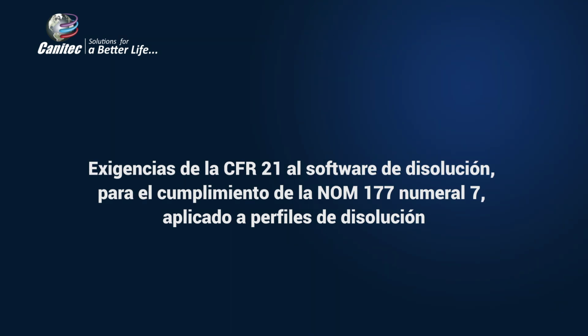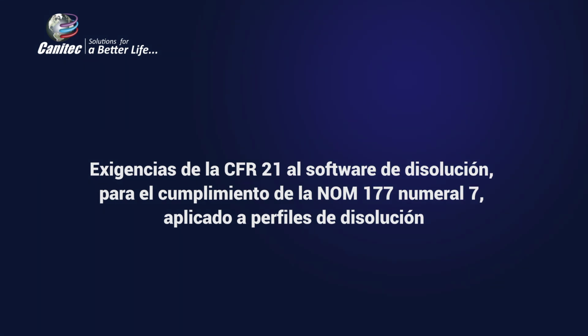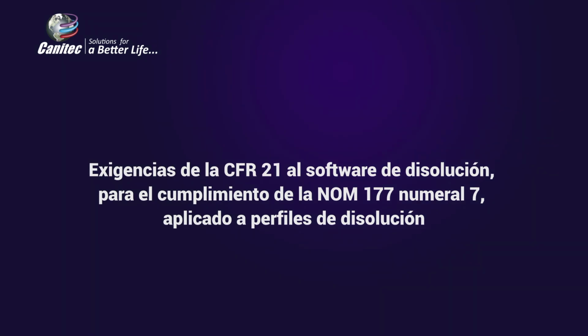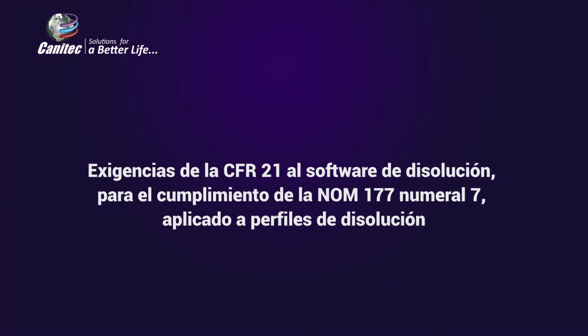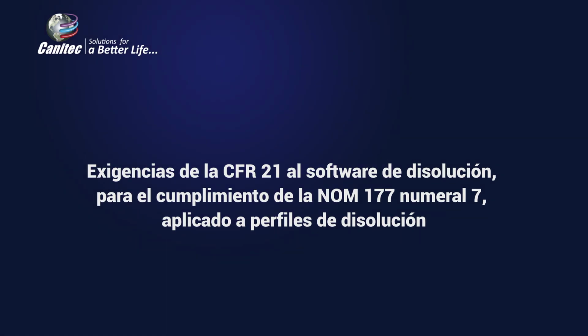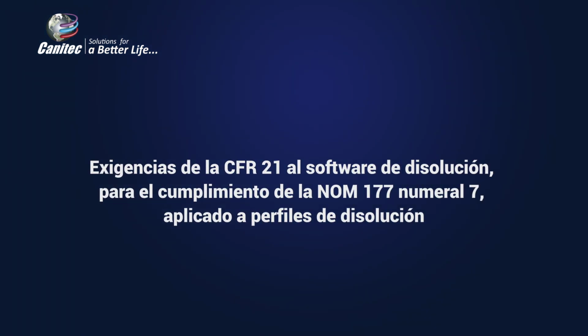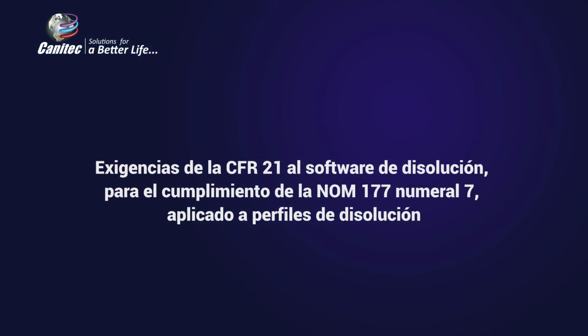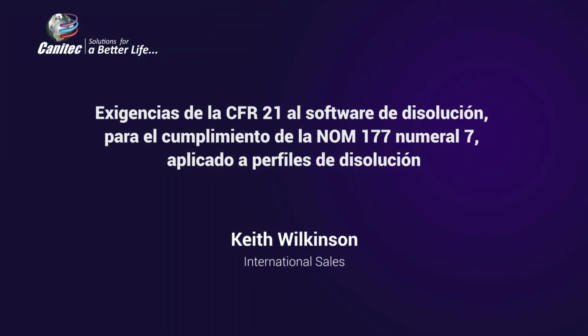On the software as well, if you wanted to, you can see the percent dissolution as the experiment is proceeding. You do not have to wait until it's stopped. And we also have statistics where you can look at the statistics of the experiment and you can view that in real time. Okay, so we have that. The test is completed and we do not have to save the record, it's saved automatically.